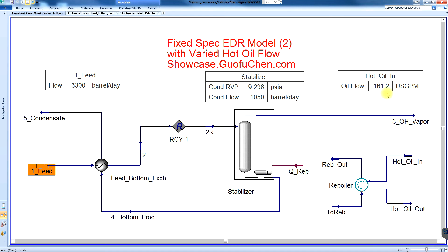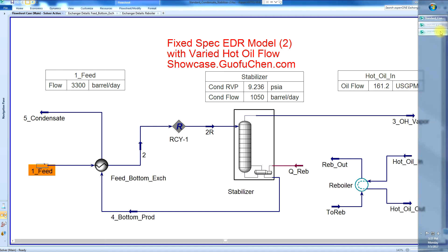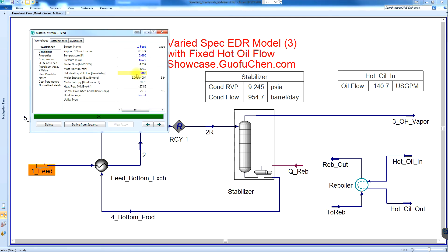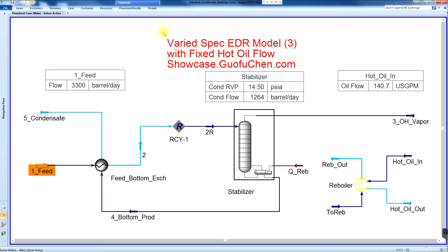The customer may say they don't have the requested additional hot oil flow — then what? A third model is set up to answer this challenge with a fixed hot oil flow rate. Simply input the 3300 barrel per day feed and wait for the simulator to converge. Once it is finished, the new product RVP becomes about 14.5 PSI, compared to 9.3 PSI at the original design condition.